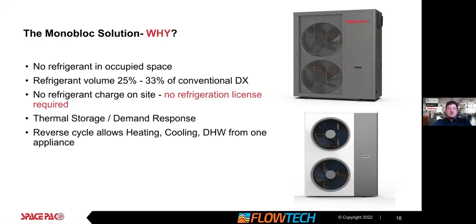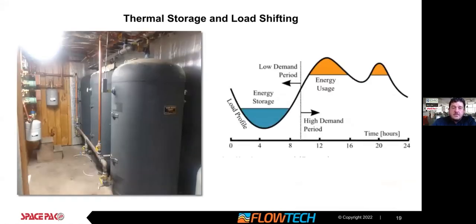Thermal storage and demand response. I've got a slide on this and I'll talk next on that one. But here's the big one too with this: all the things you can do with the monoblock heat pump, even the split unit, is the heating, cooling, and domestic hot water from one outside appliance. Domestic has some considerations, but at the very least, a preheat for domestic hot water, heating and cooling, all from one outside appliance on a very low amp draw. Big benefit of these units. Thermal storage and load shifting.